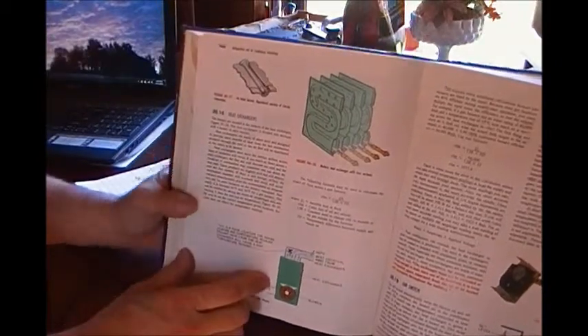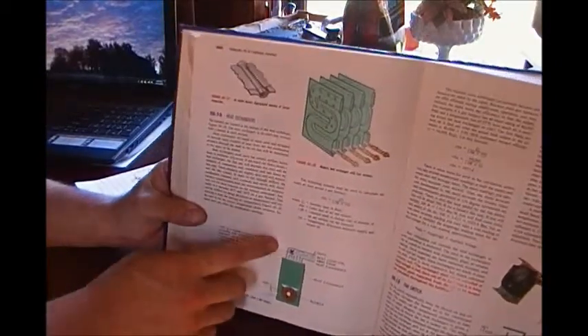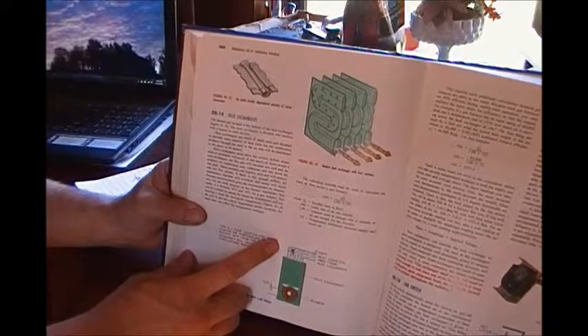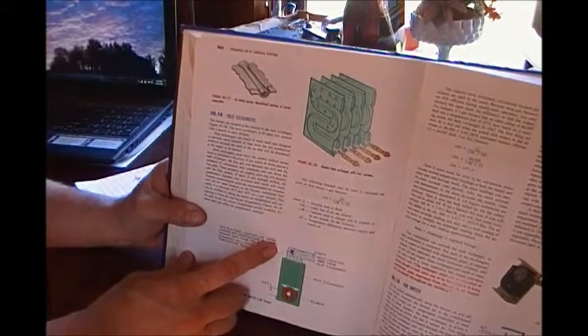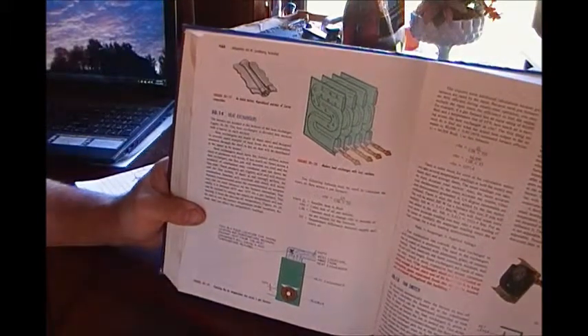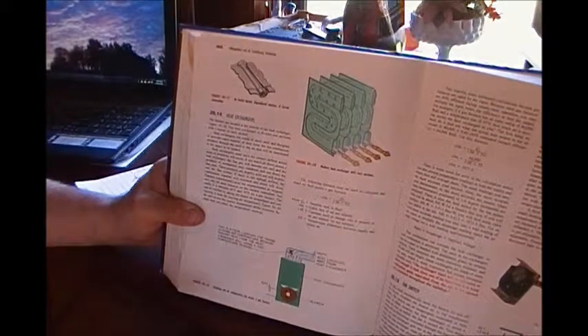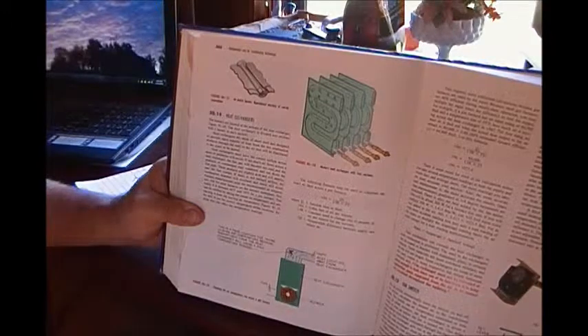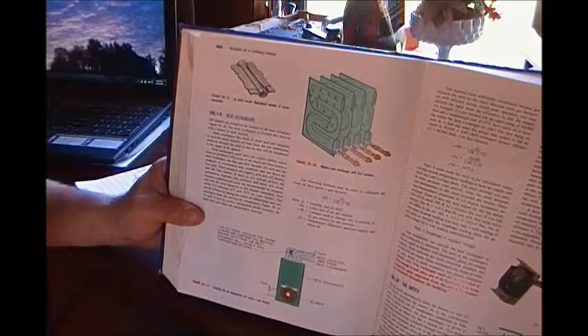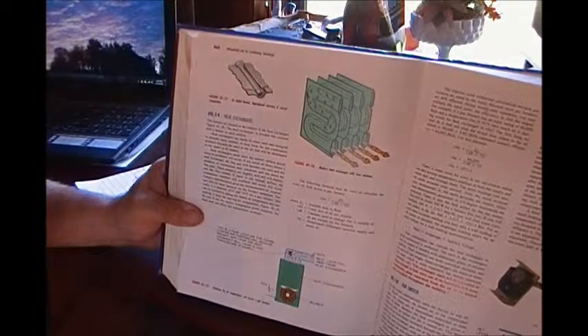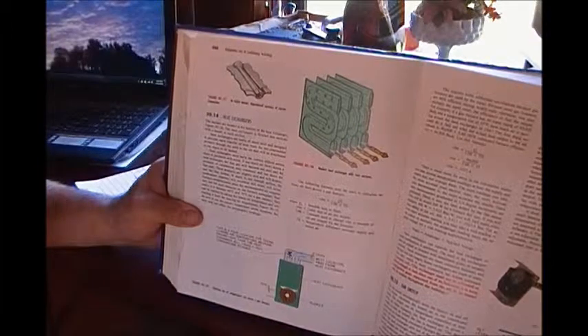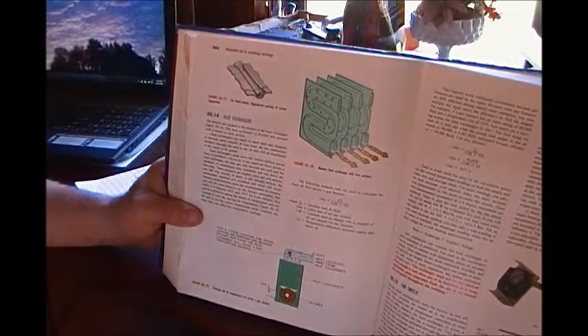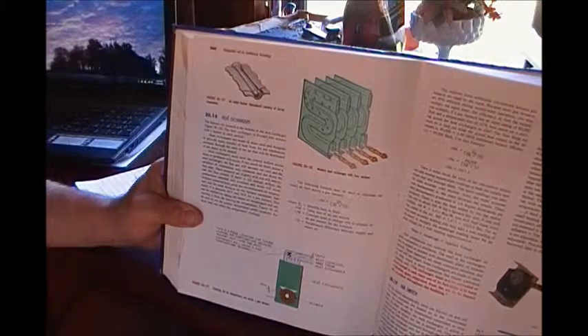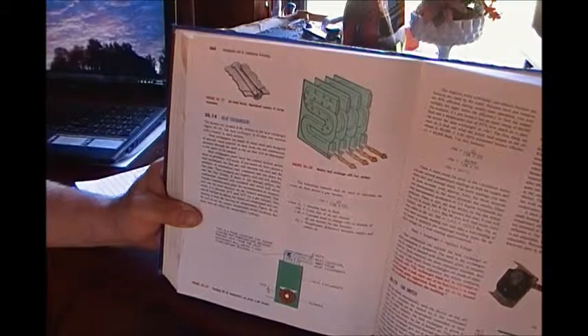Because too much gas and you'll have too much temperature going over your exchanger, which will kill your exchanger, not to mention it will run a high gas bill. Not enough, and the furnace will hardly even burn enough to make temperature. I've seen it where they've been so low that they didn't even burn the oils off the exchanger, and after I set the 3.5, the furnace started working properly.